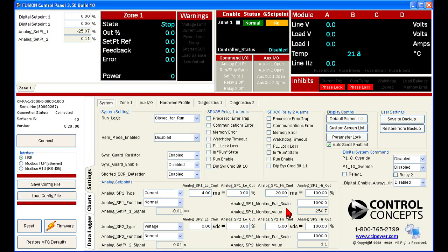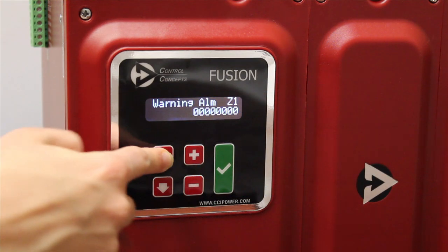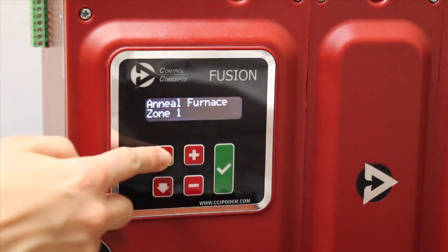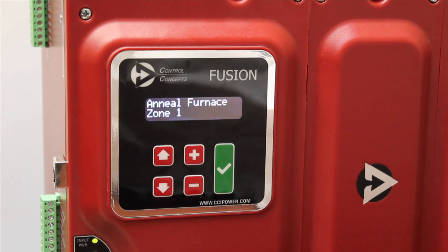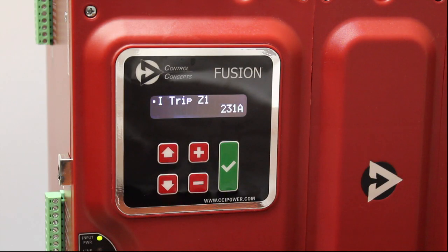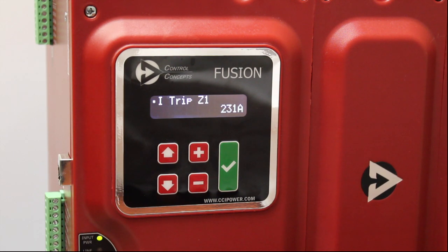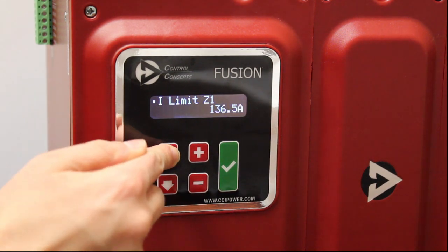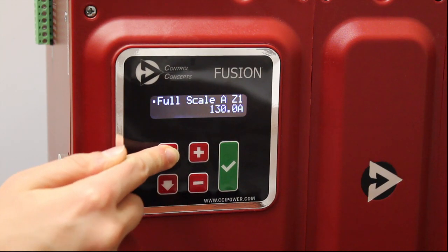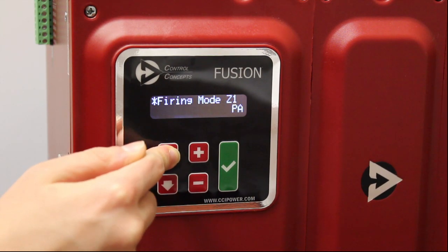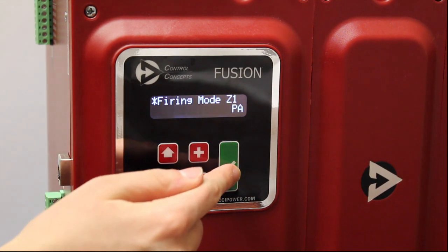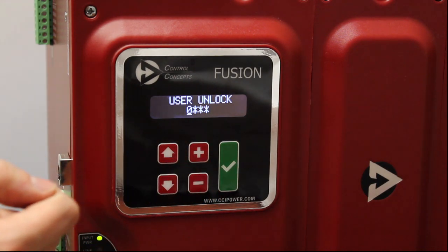You must then reset the controller for the changes to take effect. We can now scroll on the display to see our custom text. Many parameters can be edited from the controller display itself. Parameter lock prevents users from changing specific parameters unless they enter the right password. By default, this password is 4000.